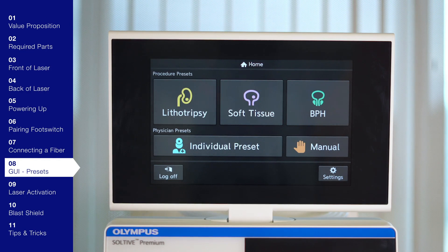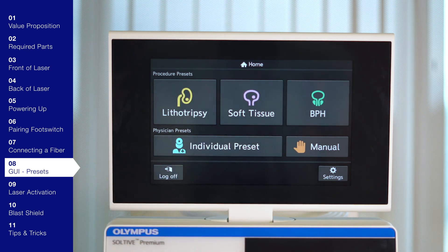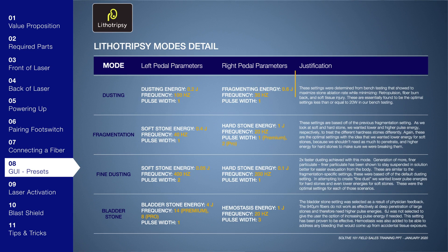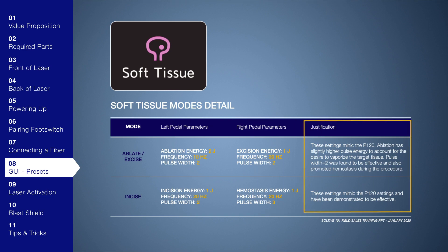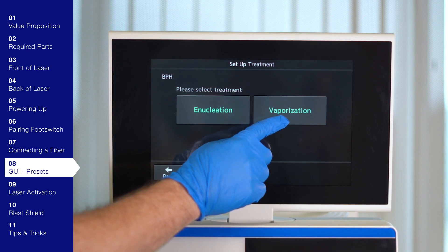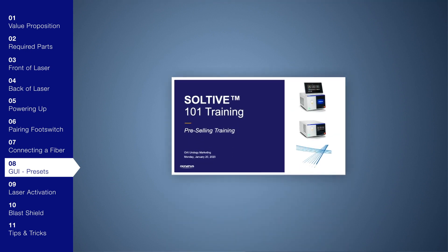Now the Soltive laser is powered on, the foot switch and fiber are connected, and we're ready to choose the procedure and adjust laser parameters. We recommend using the presets available within lithotripsy, soft tissue, and BPH procedures. Within lithotripsy you have dusting, fragmentation, fine dusting, and bladder stone modes. From the lithotripsy mode's detail, you can see the recommended parameters and justification for the left and right pedals. Within soft tissue, you have ablation and incision modes. Within BPH, we have enucleation and vaporization modes, each with recommended presets for the left and right foot pedal. All these charts can be found in the Soltive 101 Field Sales Training PowerPoint.